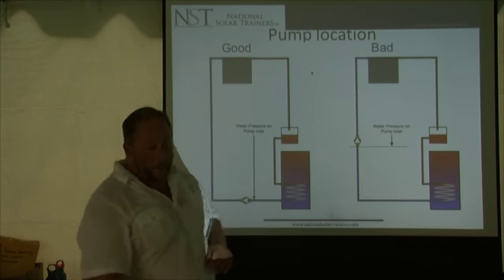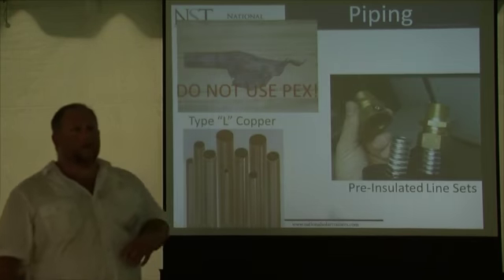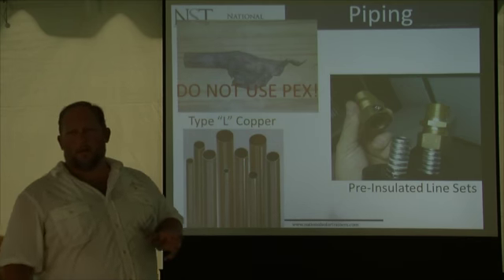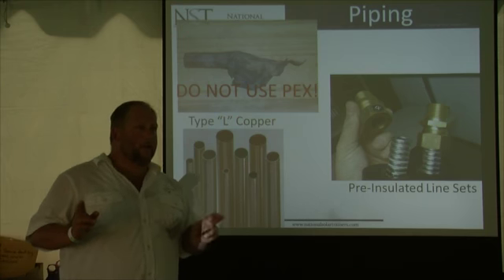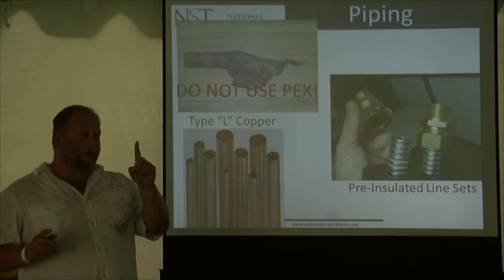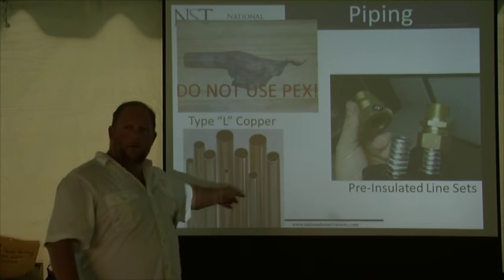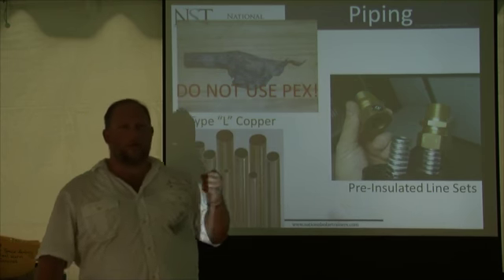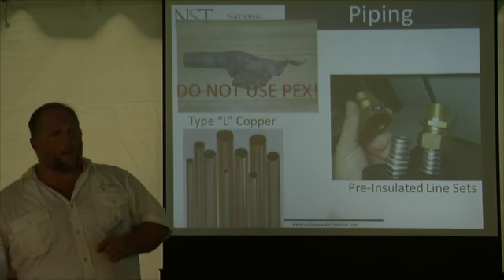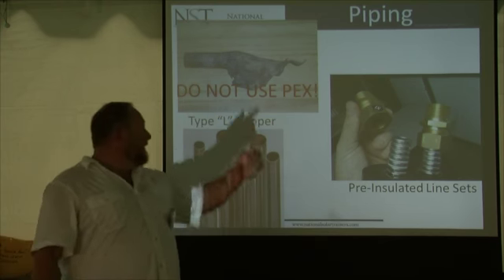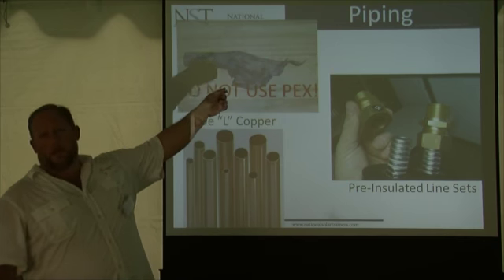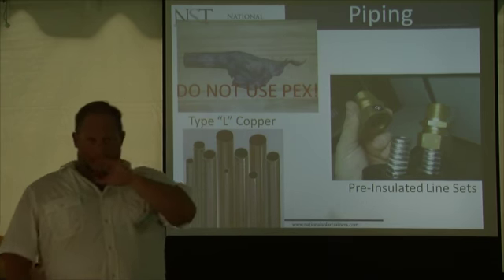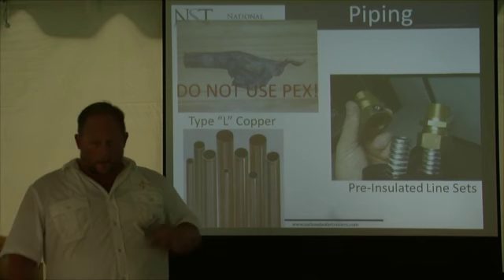Pump location for drainbacks is important. Now, the piping you're going to use can basically be one of two types - there's one exception I'll mention, but basically copper or flexible stainless steel. It's got to handle really high temperatures and high pressure. PEX tubing is not acceptable, any type of plastic, certainly no PVC, can't handle the high temperatures. So it has to be copper or flexible stainless steel.